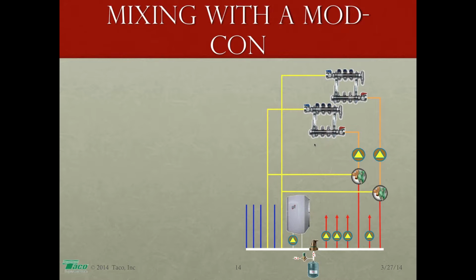Let's say you have a job where you have some panel radiators, you have some high temperature radiant floor heating in between the floor joists, and then you have some radiant floor heating in the slab. At that point, mixing with a modulating condensing boiler is going to make some sense. And in fact, it's actually going to have some substantial benefits. Here we show the header.